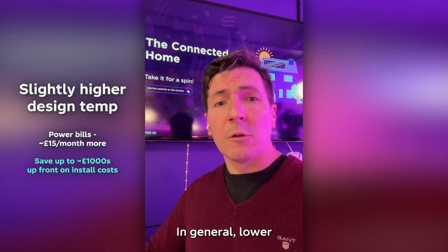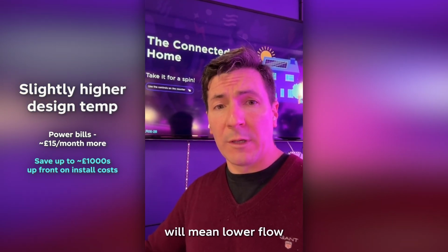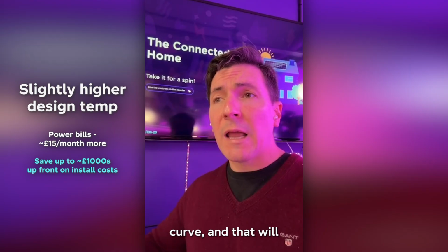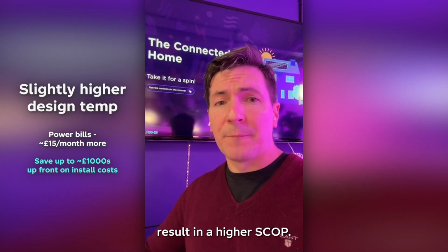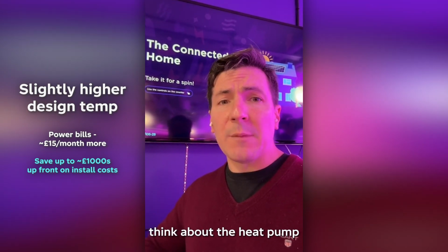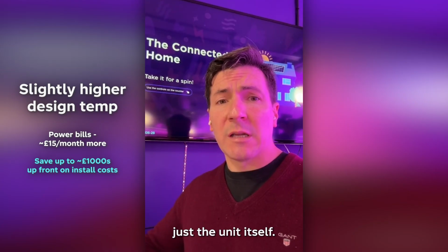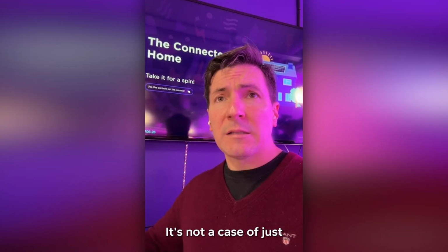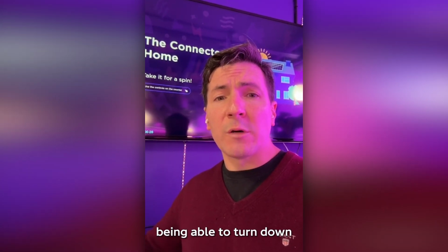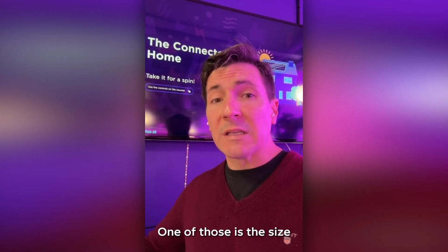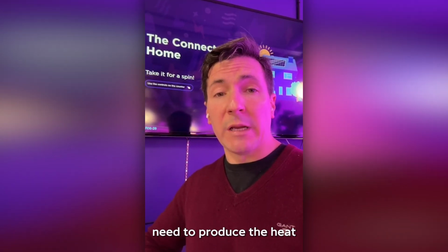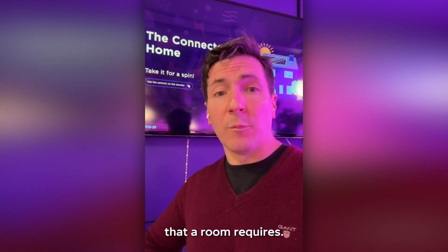In general, lower design temperatures will mean lower flow temperatures across the curve, and that will result in a higher SCOP. But it's important to think about a heat pump as part of a system, not just the unit itself. It's not a case of just being able to turn down the design temperature without thinking about other factors. One of those is the size of the radiators you need to produce the heat that a room requires.